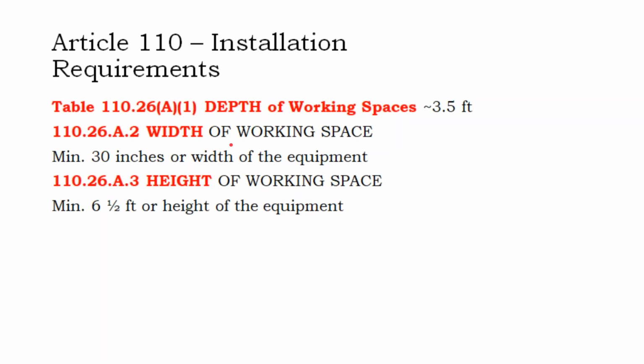Well, there's another dimension, which is depth—how far out this is. Because if you needed to get to these breakers in here, you'd need to open up that cabinet and then you're leaning over the battery cabinet. National Electric Code says you only have 6 inches of differential between one electrical box that's above another. So this is actually a code violation because we don't have that—it violates the 6 inches of depth.